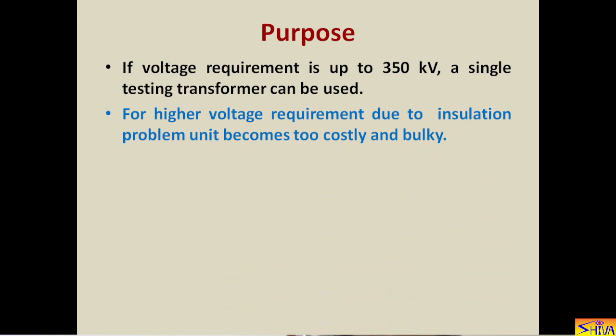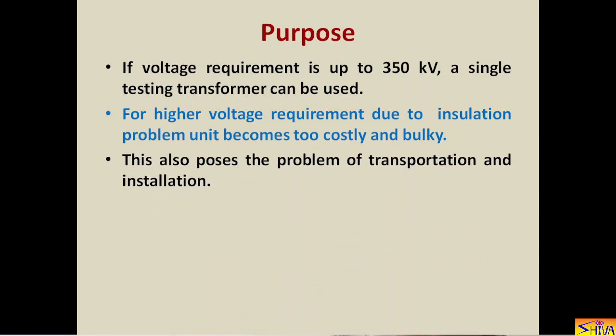For higher voltage requirements, due to insulation problems the unit becomes too costly and bulky, because the cost of insulation is proportional to the square of the voltage. So if we go beyond 350 kV, the cost of insulation becomes too high and the insulation requirement increases, making the unit costly as well as bulky. This also poses problems of transportation and installation because the unit becomes too heavy.